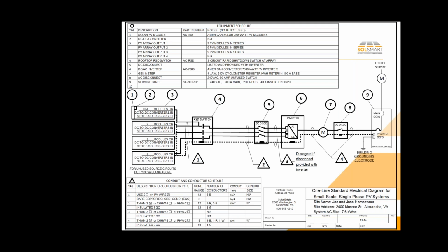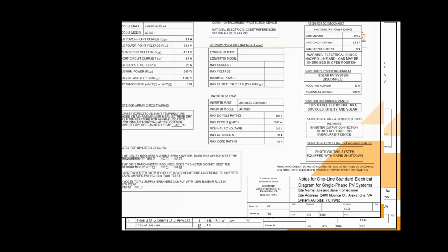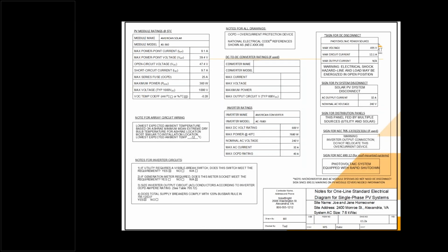So that's the basic layout and the wiring. And so the wiring coming from that 40 amp circuit breaker is number 8 conductor, which is the standard size, with the number 10 ground. All right, here's the notes pages, and this outlines the details of the module, the AS360 module.